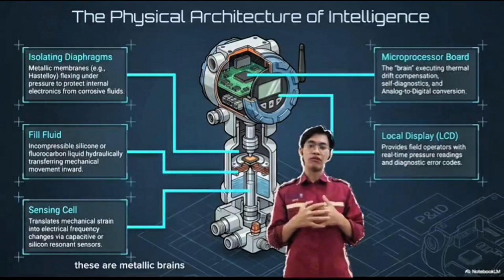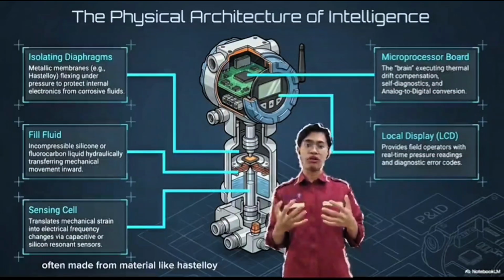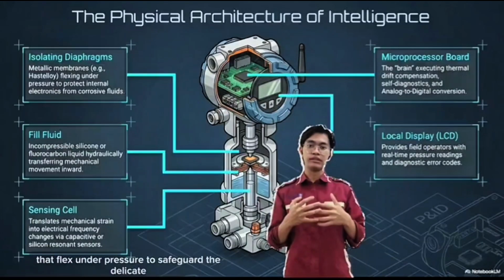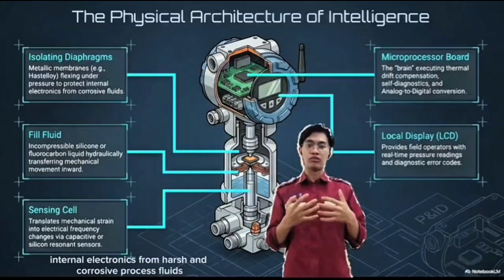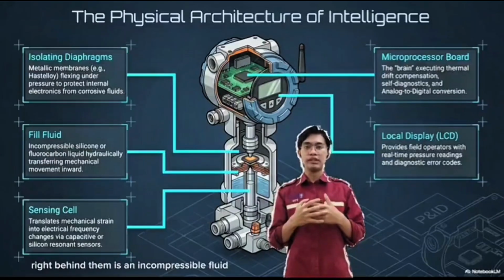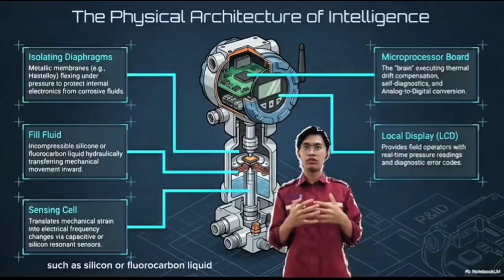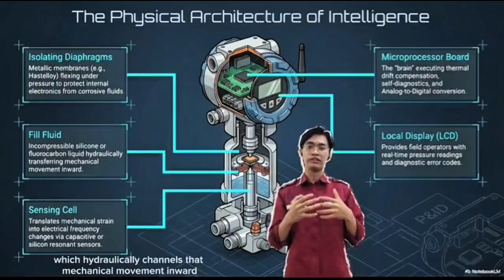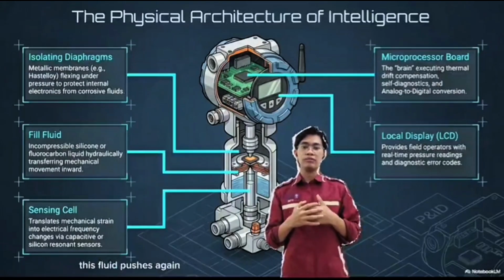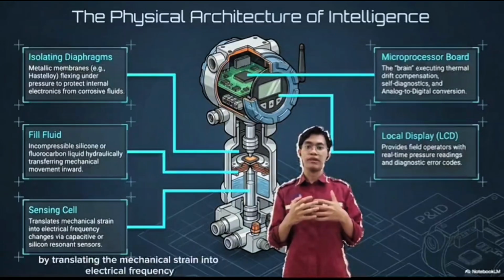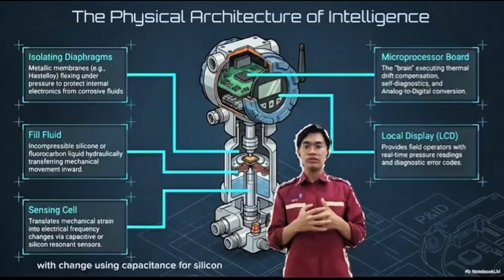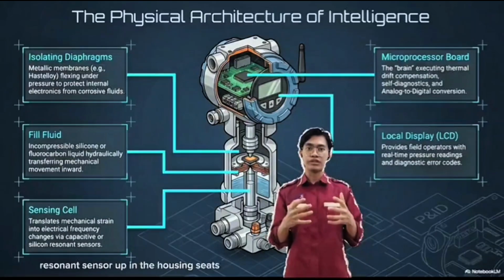These are metallic membranes, often made from material like Hastelloy, that flex under pressure to safeguard the delicate internal electronics from harsh and corrosive process fluids. Right behind them is an incompressible fluid such as silicone or fluorocarbon liquid, which hydraulically channels that mechanical movement inwards. This fluid pushes against the sensing element, translating the mechanical force into an electrical signal, using capacitance or a silicon resonance sensor.